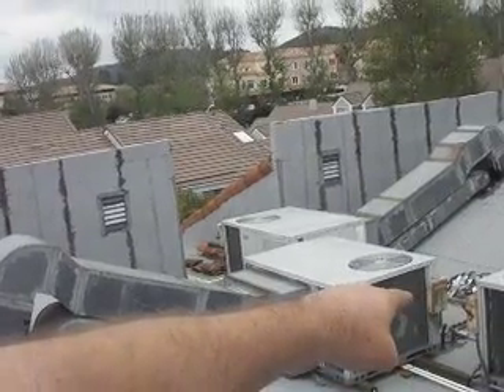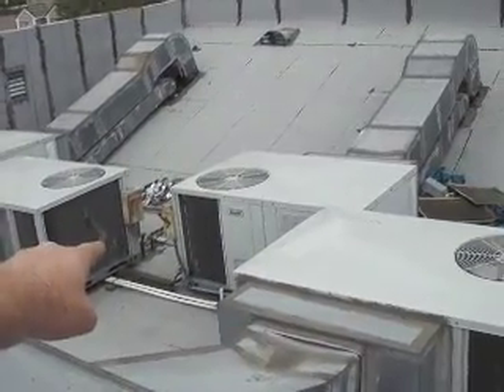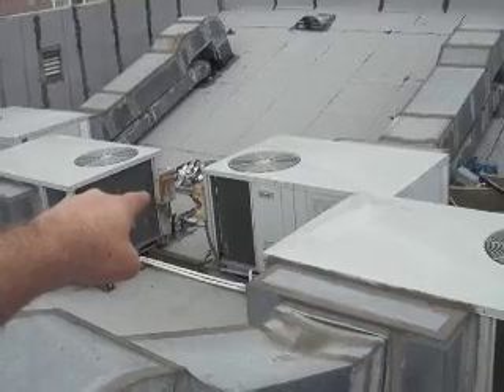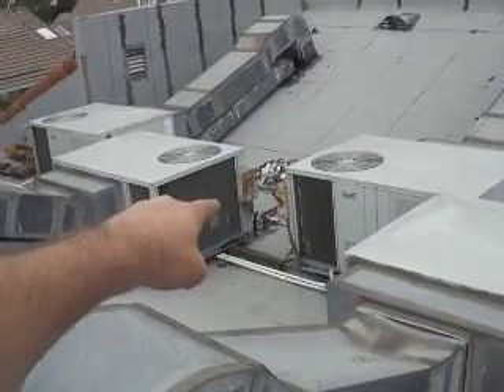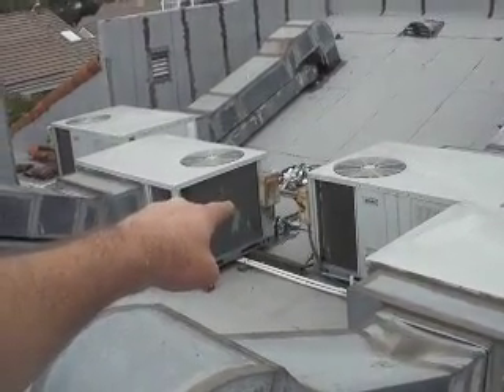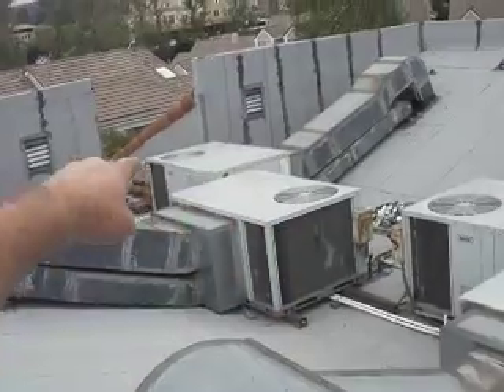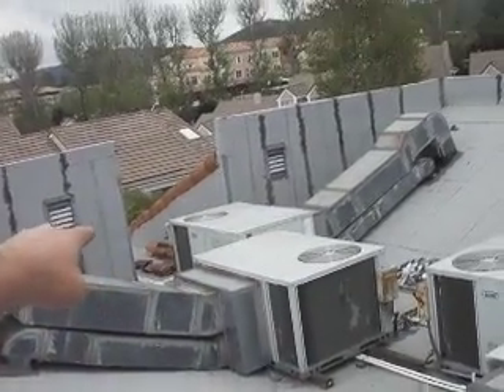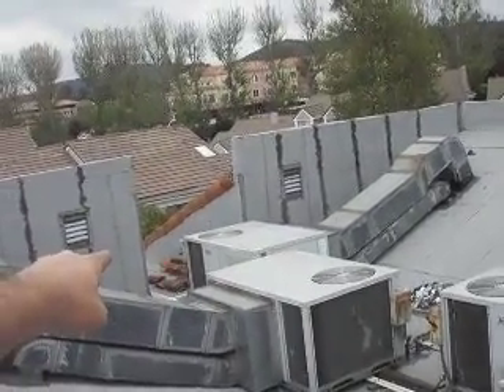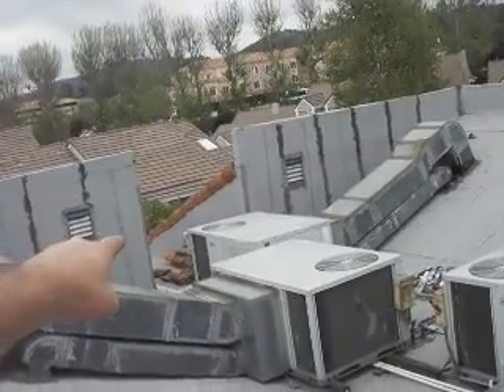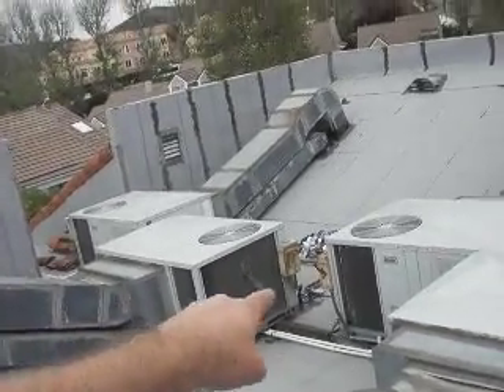And this one right here too, I believe this one has a cracked heat exchanger up on the heater, and it has refrigerant leaks as well. So when we run the heat, we really run off this one over here on the end, which doesn't do too bad, but if it's really, really cold out, then there's a little bit of a problem just preheating the theater.